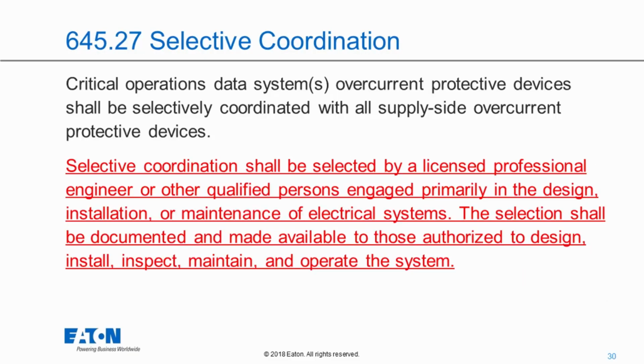Moving on to other critical systems that require selective coordination. Here we go into Article 645, which covers critical operation data systems. So we're talking about data systems that are essential for national security or perhaps public safety. We just added some additional text that is, again, in other sections of the code where selective coordination is required. So this really is just having consistent language, and we just identified the importance of the selection being done by a qualified person and that it needs to be documented as we have in other sections of the code.